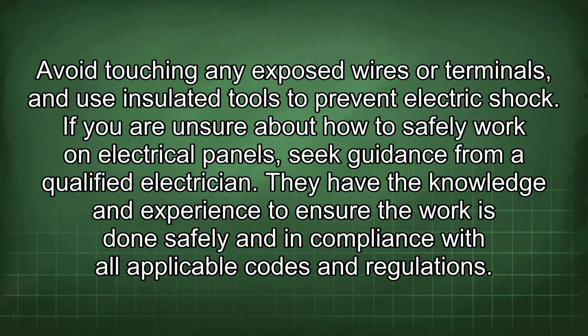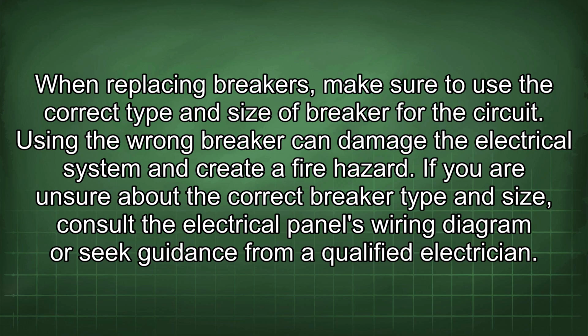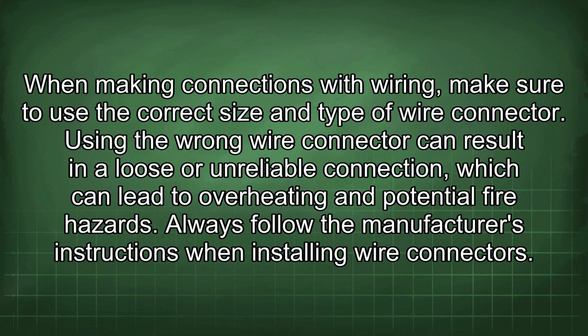When replacing breakers, make sure to use the correct type and size of breaker for the circuit. Using the wrong breaker can damage the electrical system and create a fire hazard. If you are unsure about the correct breaker type and size, consult the electrical panel's wiring diagram or seek guidance from a qualified electrician. When making connections with wiring, make sure to use the correct size and type of wire connector. Using the wrong wire connector can result in a loose or unreliable connection, which can lead to overheating and potential fire hazards. Always follow the manufacturer's instructions when installing wire connectors.